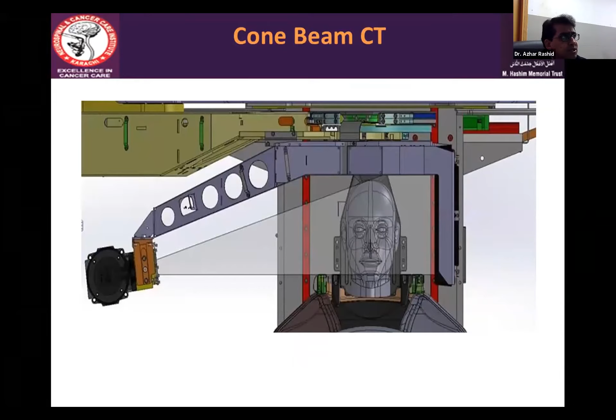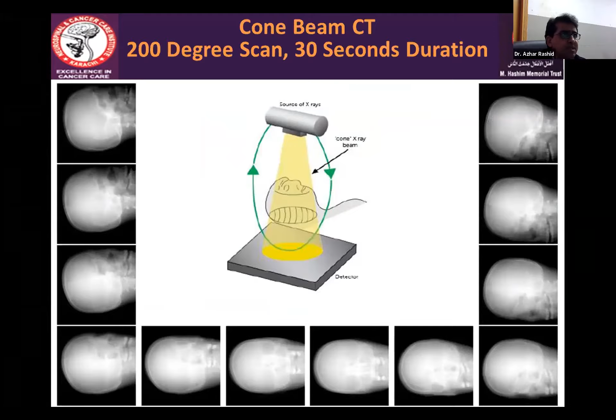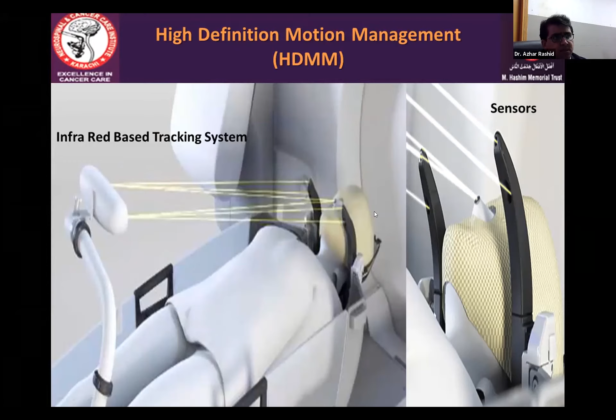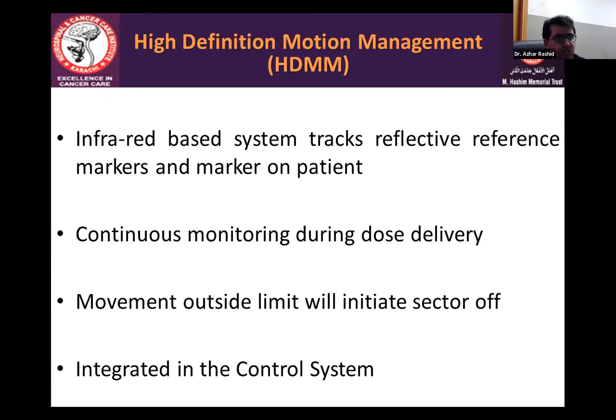This is the cone beam CT internal structure, and the 200-degree scan is acquired like other cone beam CTs. And this is the high definition motion management in this system. There is an infrared-based tracking system lying at the foot end of the patient, and there are sensors placed on the head end and the nose of the patient. They detect the motion if there is any. This is continuous monitoring during dose delivery, and movement outside the limit will initiate sector off, integrated in the control system. And this is the graphical representation.